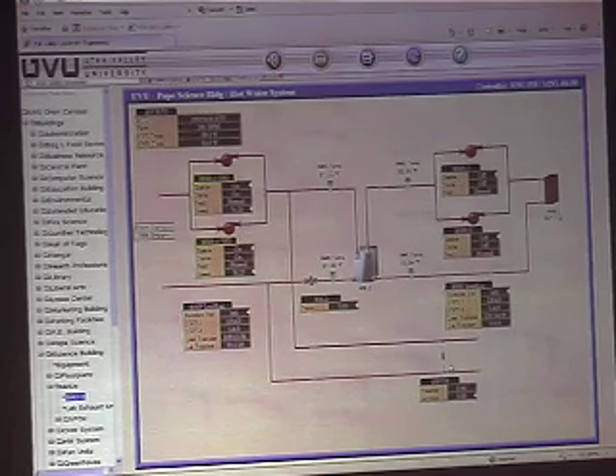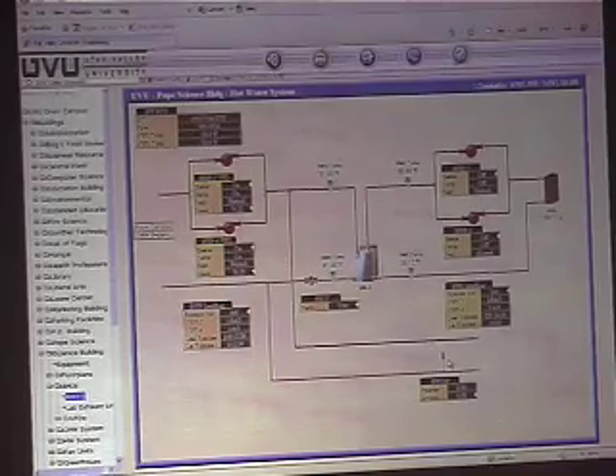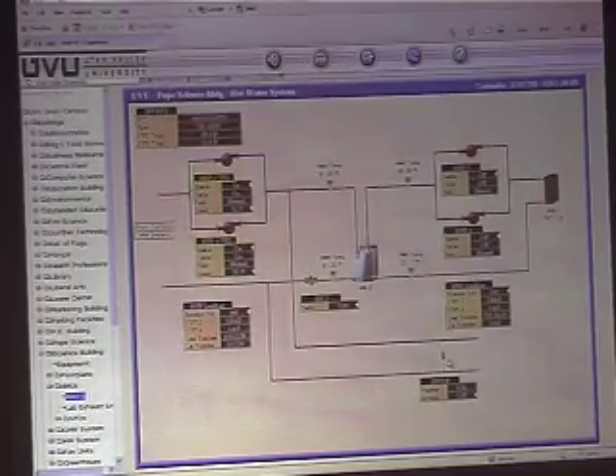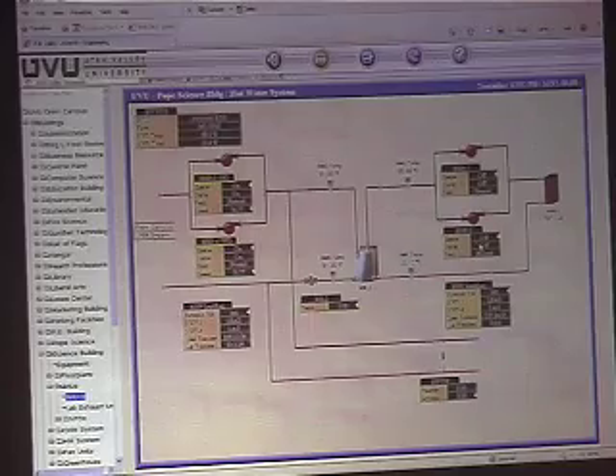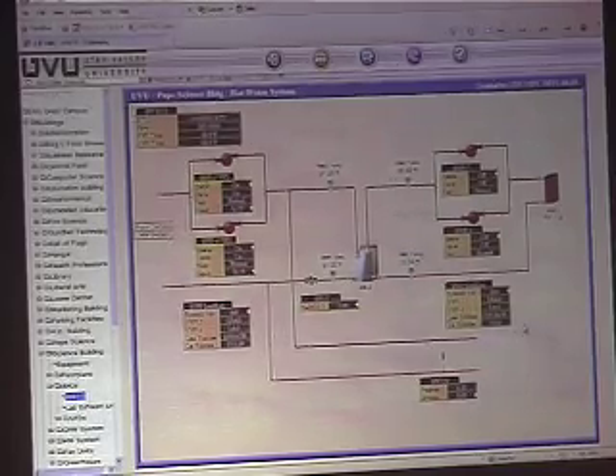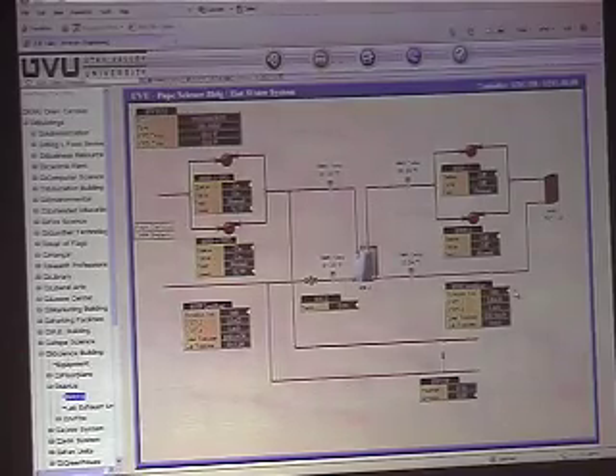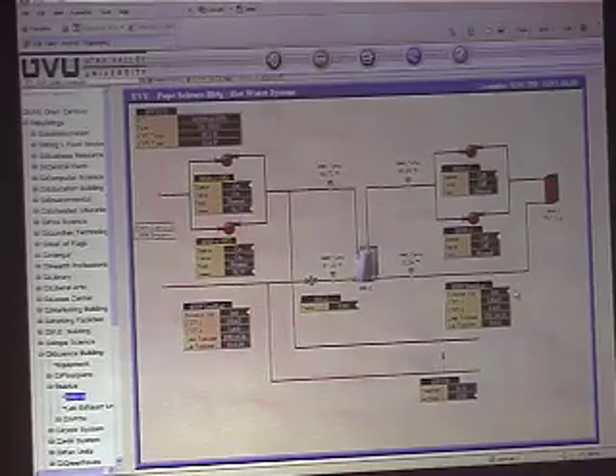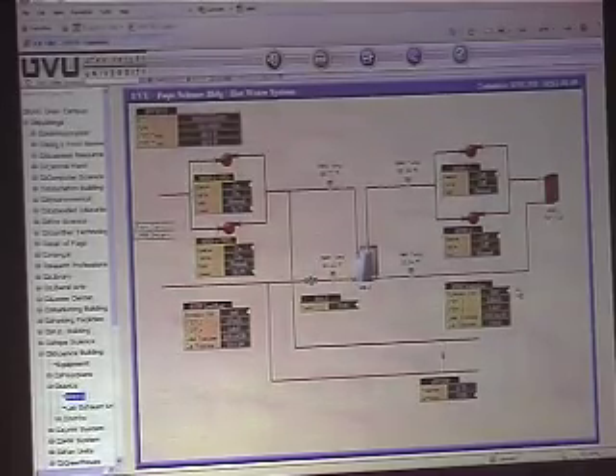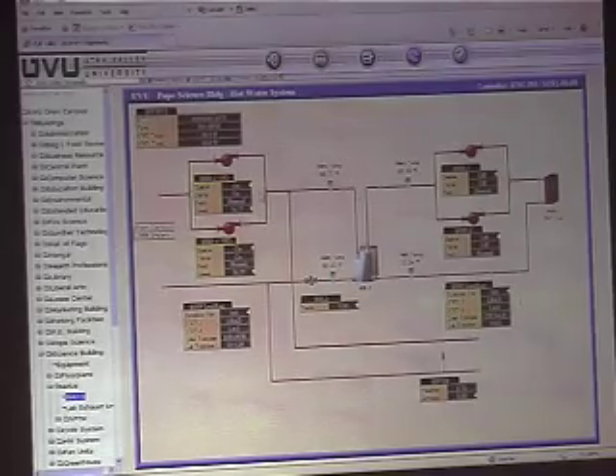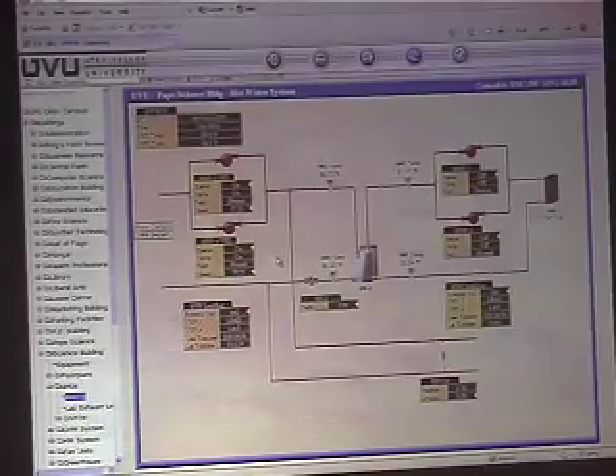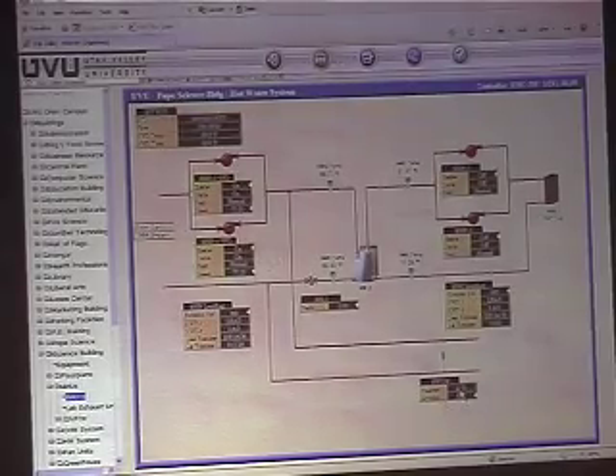their speed is controlled off of the hot water differential pressure transmitter right here. And I'll show you when we do the walkthrough where it's located, but it's down on this level above one of the ceilings in one of the classrooms. So these pumps are set up on a lead lag schedule. Every 168 hours of runtime, which is basically a week's worth of hours, it'll rotate the lead pump. So it's only meant for one of these to be running at a time, unless, in this case where these are both on right now, it's just because there's enough pressure demand in the building that it's causing these 2 to run to give you enough flow.